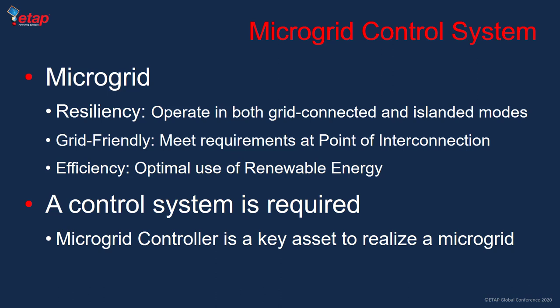For example, if there's excess renewable power compared to loads, the microgrid controller uses energy storage to absorb extra active power and prevent export to the grid. There are also requirements for active and reactive power support during disturbances. Another attribute is efficiency — a microgrid control system allows optimal utilization of renewable energy resources. With energy storage, you can do peak shaving, price arbitrage, and make the microgrid more efficient in utilizing renewables.